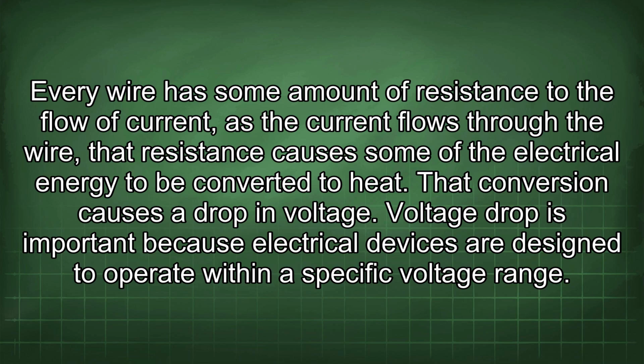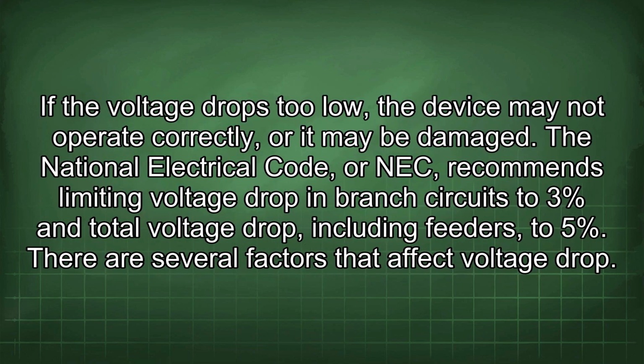Voltage drop is important because electrical devices are designed to operate within a specific voltage range. If the voltage drops too low, the device may not operate correctly, or it may be damaged. The National Electrical Code, or NEC, recommends limiting voltage drop in branch circuits to 3% and total voltage drop, including feeders, to 5%. There are several factors that affect voltage drop.